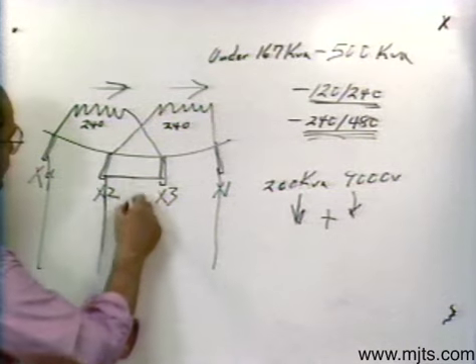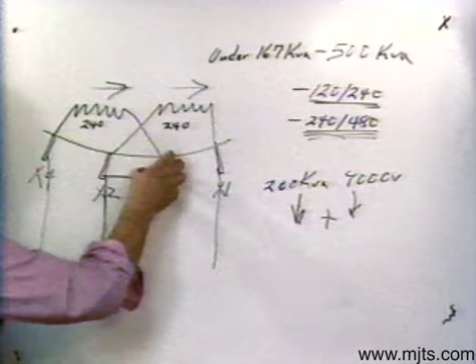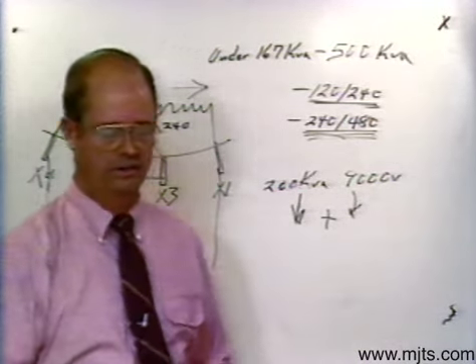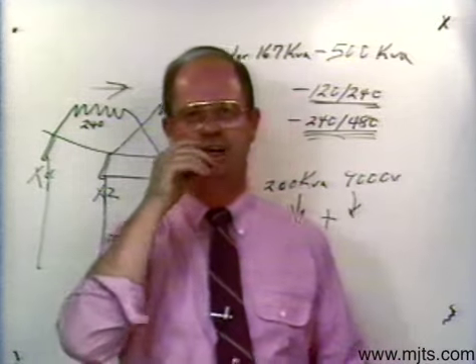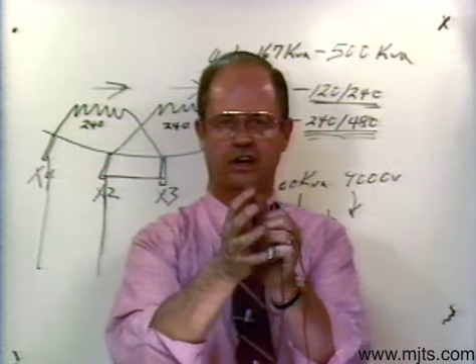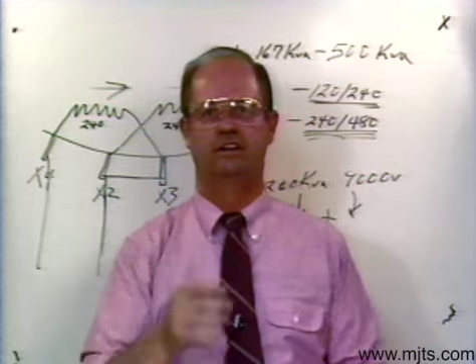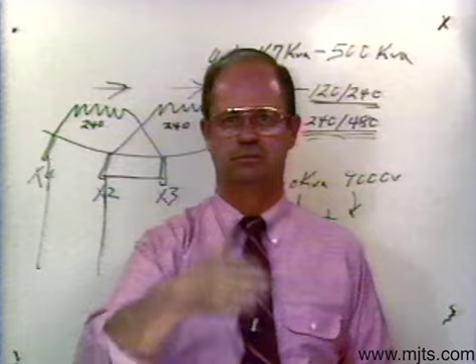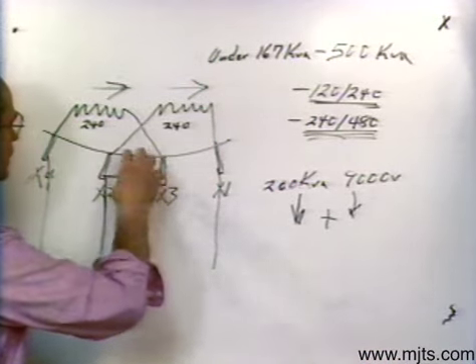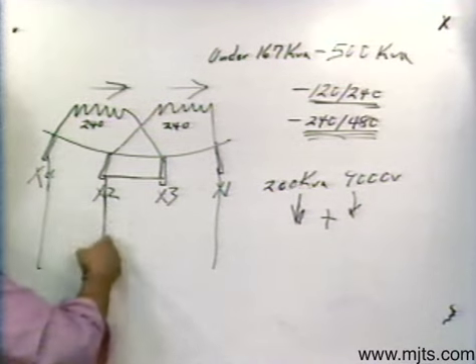Notice I wouldn't tie on to the center of the winding itself — you're normally going to tie on to the bushing. You wouldn't tie to the center because you're going to have the added spade lugs on the bushings. You can tap right on those lugs to make all your connections, rather than clamping around the center of the transformer with other connectors.